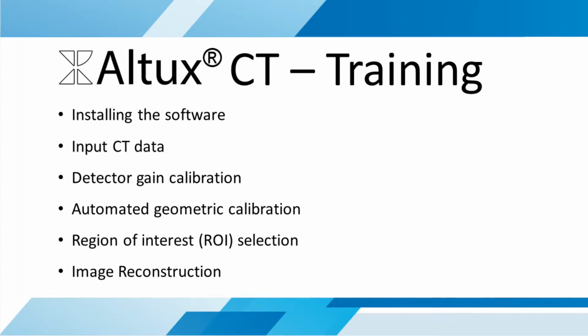We provide training on the following components: installing the software, inputting the CT data, detector gain calibration, automated geometric calibration, region of interest selection, and image reconstruction. For training on the sequence viewer and 3D viewer, please watch the next video.